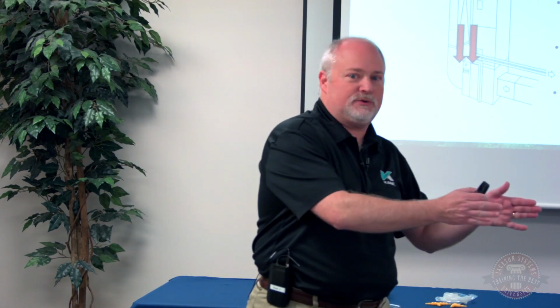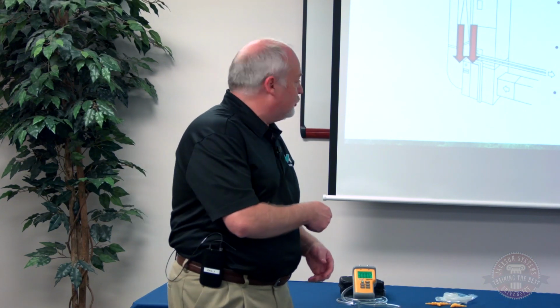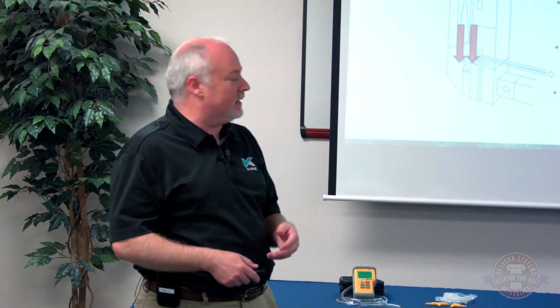Hey, maybe that's an opportunity to sell. Let's get you a 4-inch pleated filter in here that gives us enough surface area that now we can provide good filtration, but yet we have enough airflow to solve the issue that we had with the piece of equipment. We can get our proper temperature rise across the heat exchanger, it's going to last, and we're going to have a quiet system that operates as it's designed to operate.